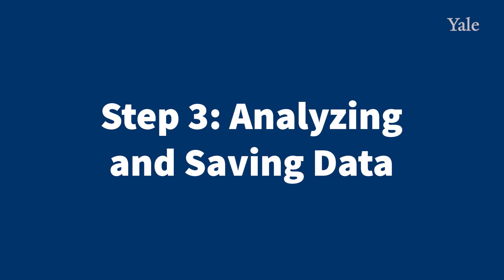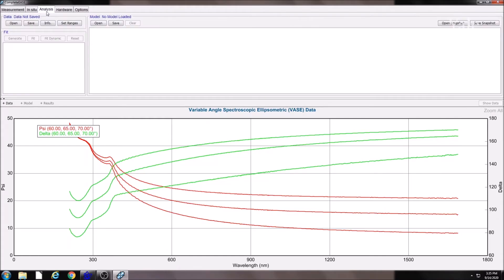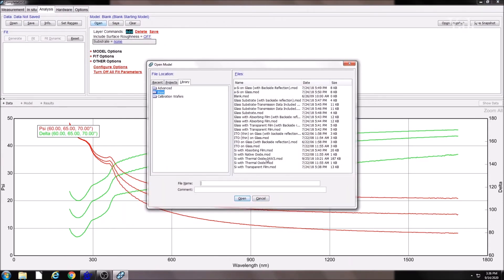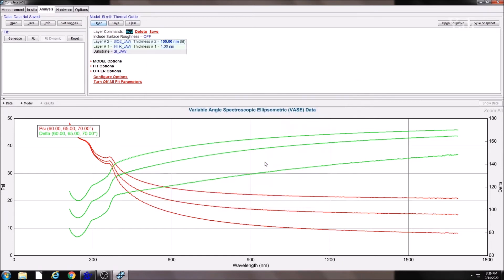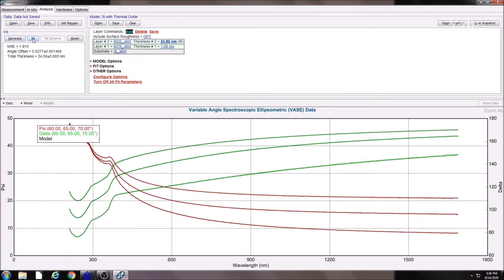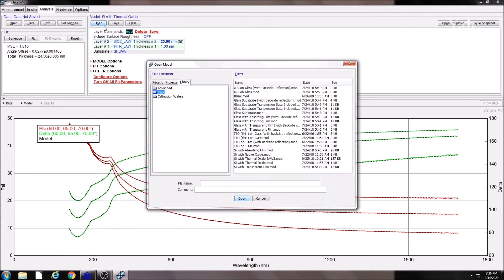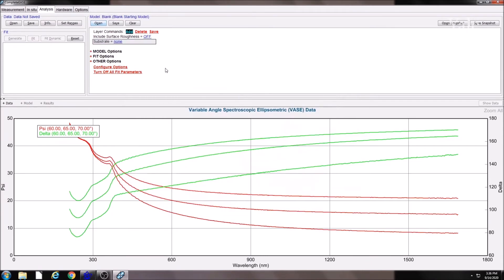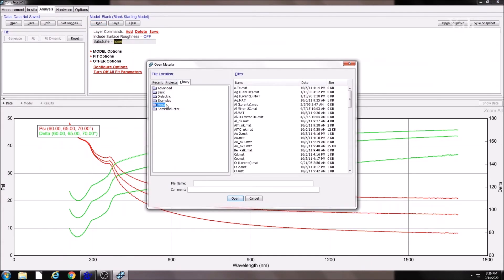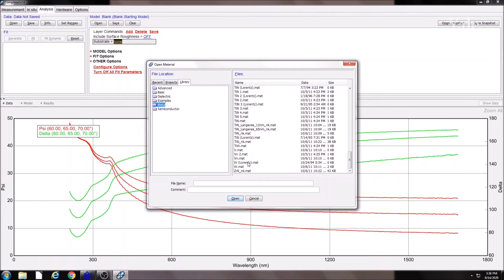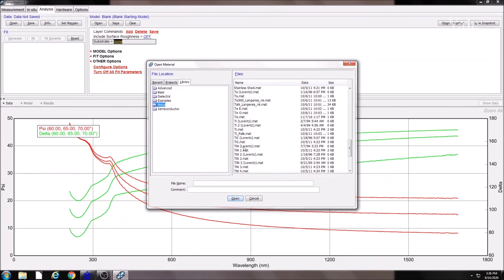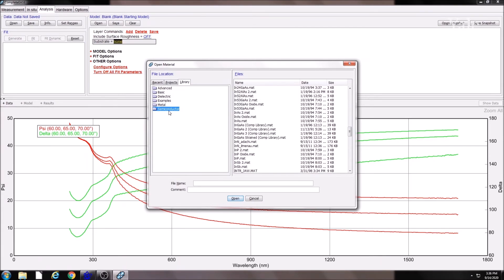Step 3: Analyzing and saving scan data. After your scan is complete, move to the Analysis tab to analyze your data. You can use one of the pre-existing models, press Generate and Fit to find the best thickness fit for your sample. You can also create a blank model and add the substrate and films using the existing library.